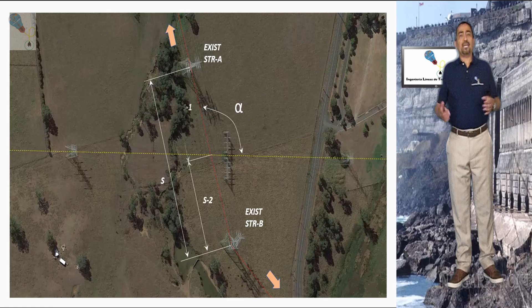Number four: we need the attachment points on each structure of all cables involved — conductor cables in each phase, each circuit, shield wires, OPGW, in a word, all the cables existing within the crossing with their identification: upper phase, middle phase, lower phase for lines with a vertical formation, or left phase, central phase, and right phase for lines with horizontal formation.